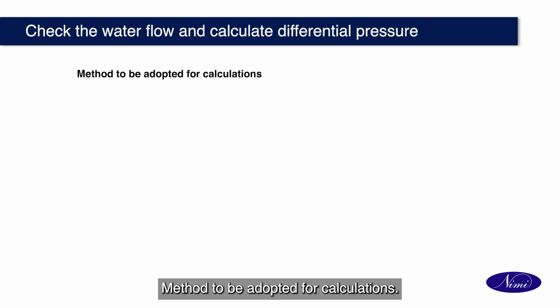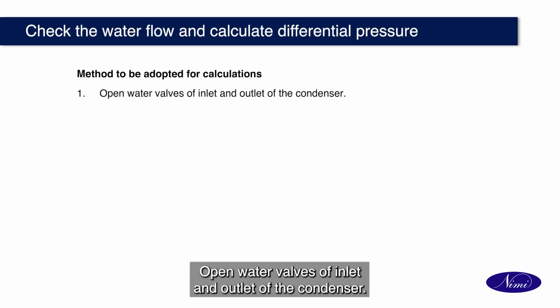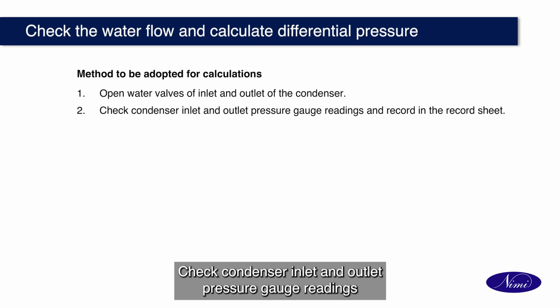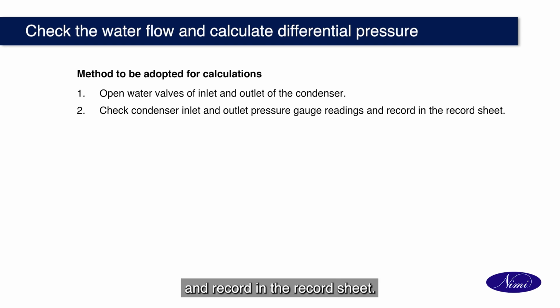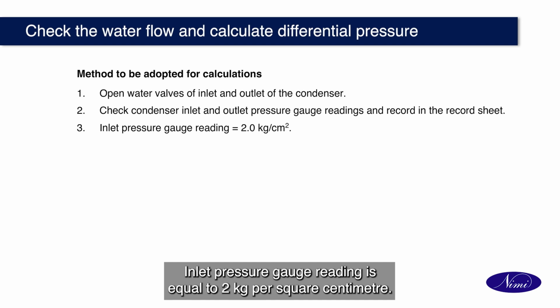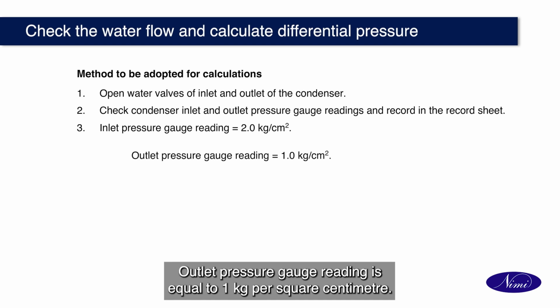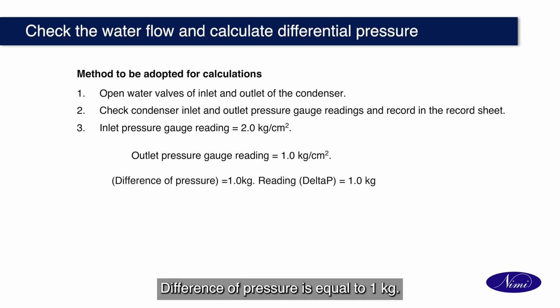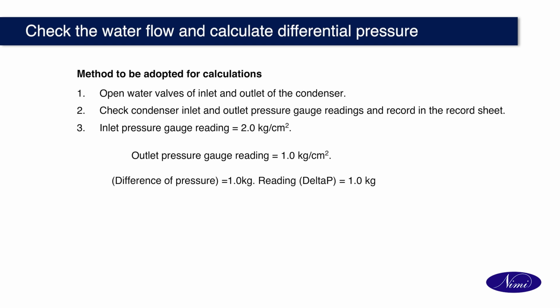Method to be adopted for calculations. Open water valves of inlet and outlet of the condenser. Check the condenser inlet and outlet pressure gauge readings and record in the record sheet. Inlet pressure gauge reading is equal to 2 kg per square centimeter. Outlet pressure gauge reading is equal to 1 kg per square centimeter. Difference of pressure is equal to 1 kg.